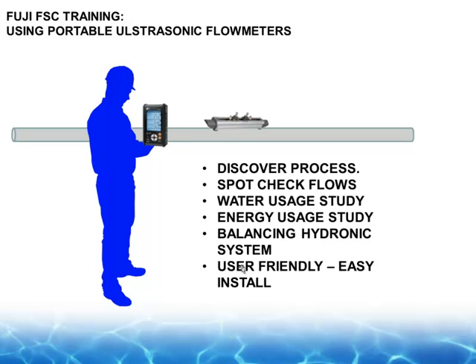It's also ideal for spot check flows. For example, you have a municipal facility full of mag meters, turbine meters, and so on. You need to do annual calibration. You're going to pull your mag meters out of line? I don't think so.